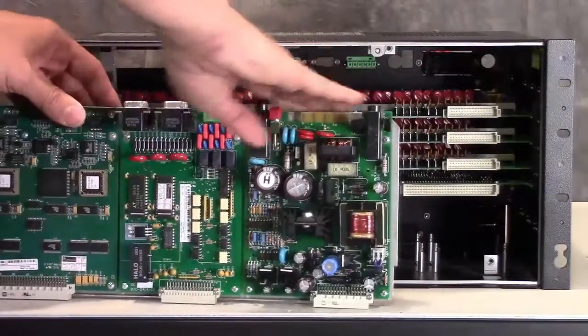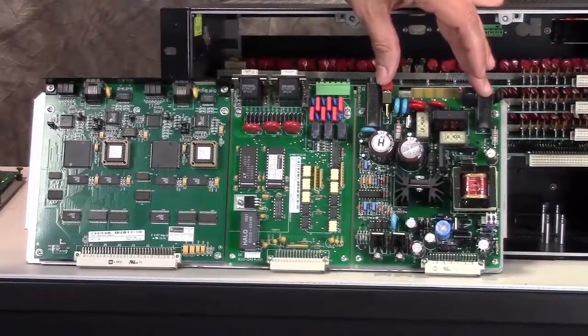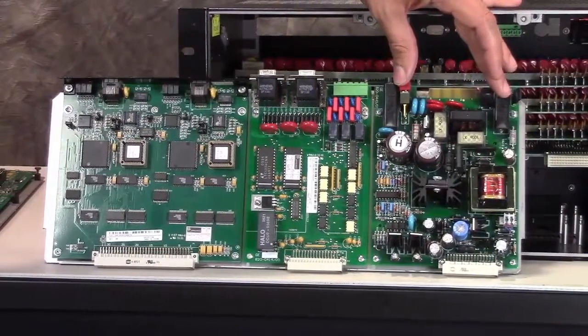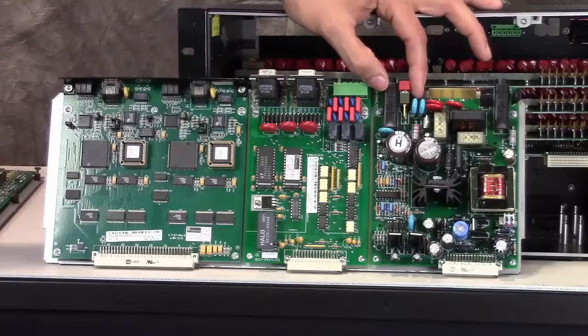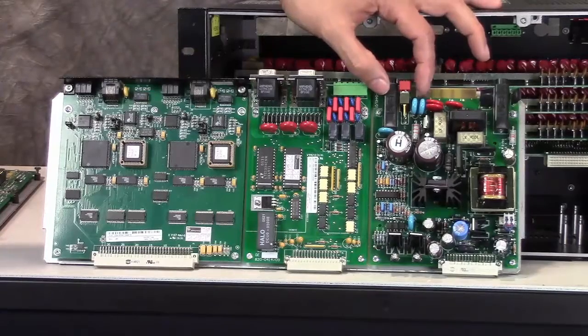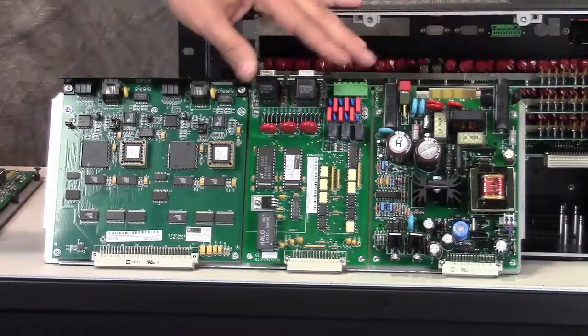The power supply can connect in there and it comes in many flavors. The available power inputs are: option one — 70 to 250 volts DC or 120 volt AC; option two — 250 volt DC or 240 volt AC; and option three — 20 to 60 volt DC. So there are three power supply options in total.